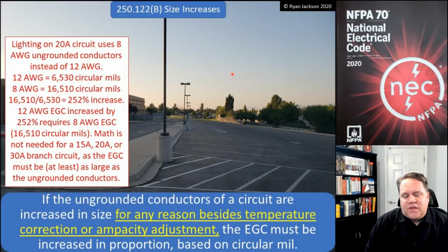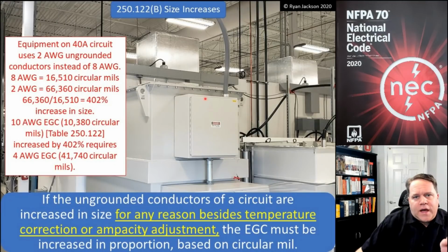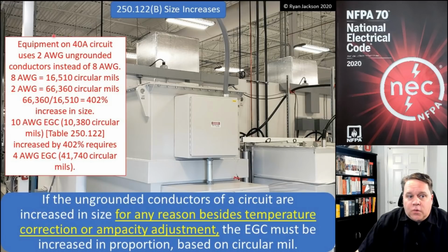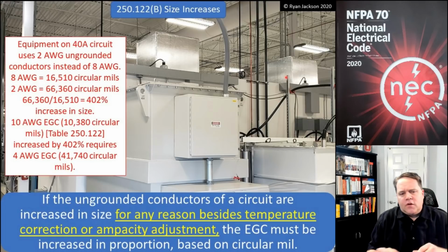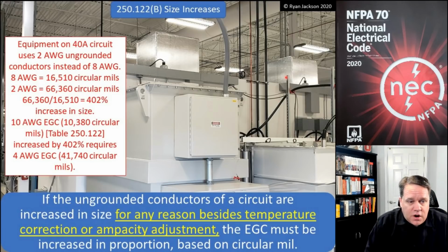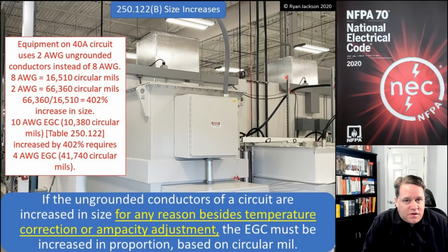So the math is easy for those circuits. If I don't have a 15, 20, or a 30 amp branch circuit, I actually might have to do a little bit of math. So here I've got a 40 amp circuit, and due to voltage drop, we used 2 gauge ungrounded conductors instead of the 8 gauge that would normally be permitted. So I have to do the same procedure. I would go back into table 8 in chapter 9.